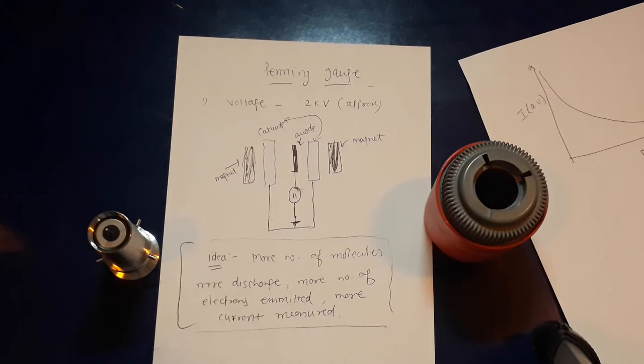The Penning gauge is used to measure very, very low pressure. It can measure up to 10 to the power minus 2 millibar to 10 to the power minus 7 millibar. It's also called a cold cathode gauge.